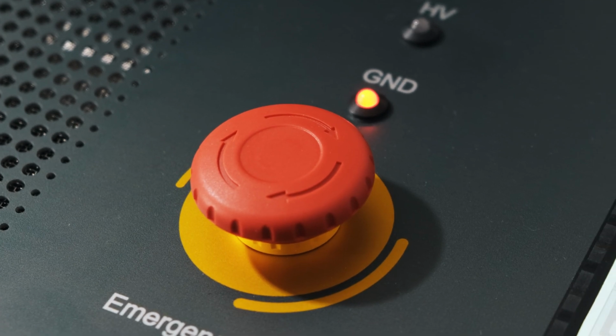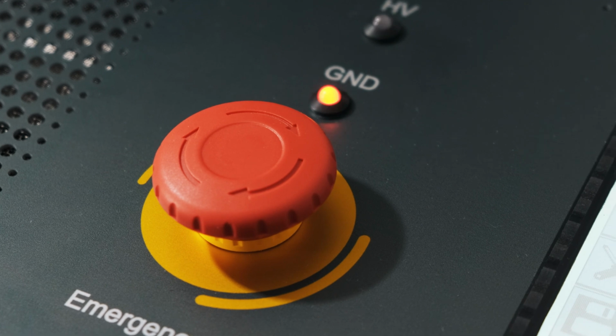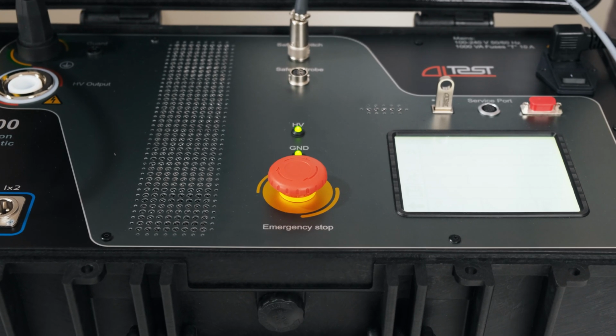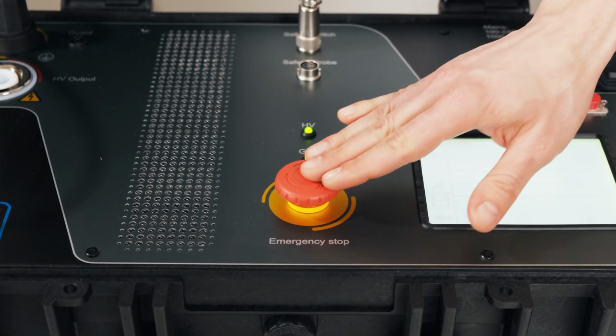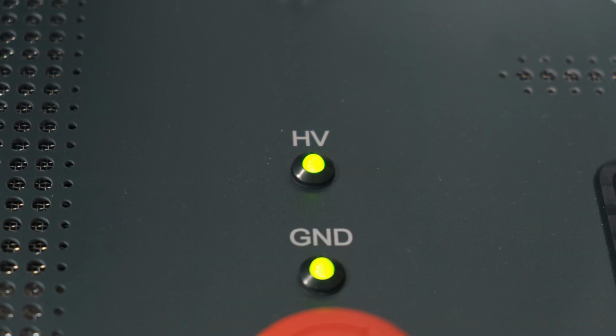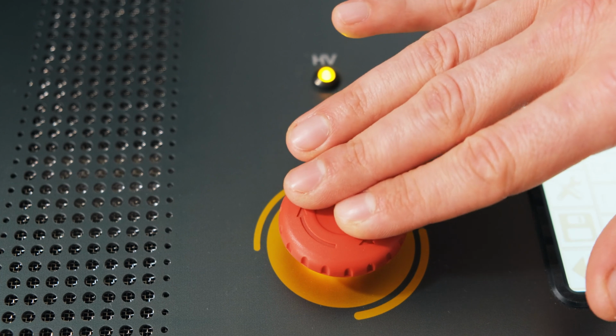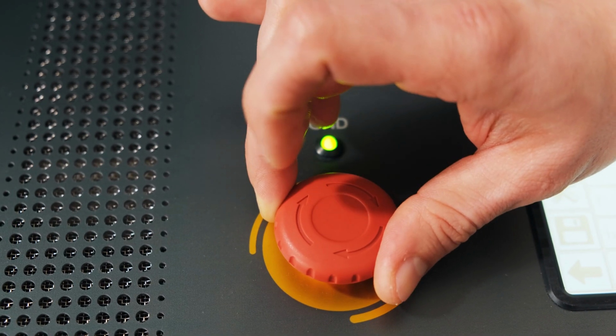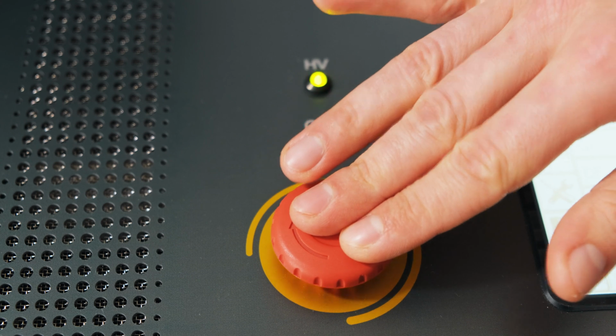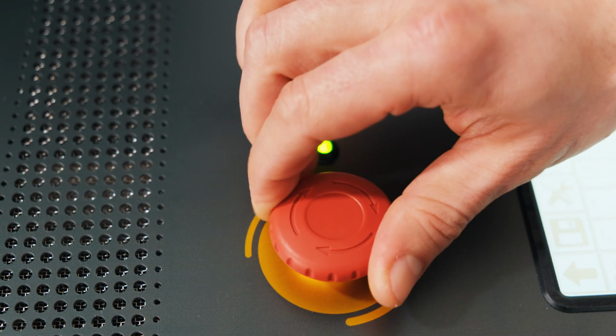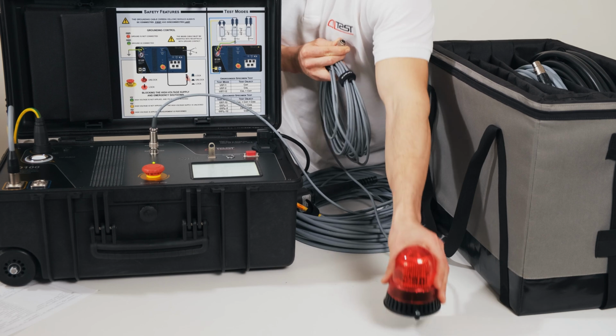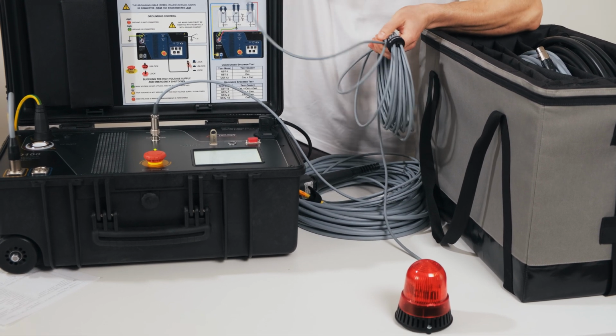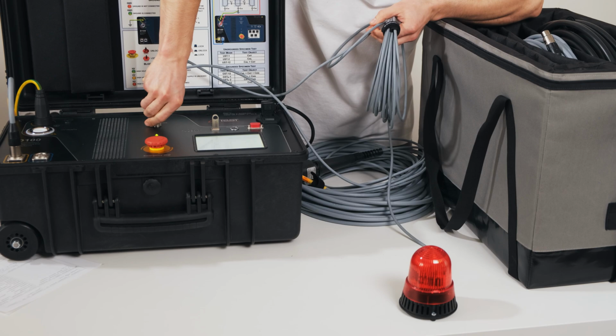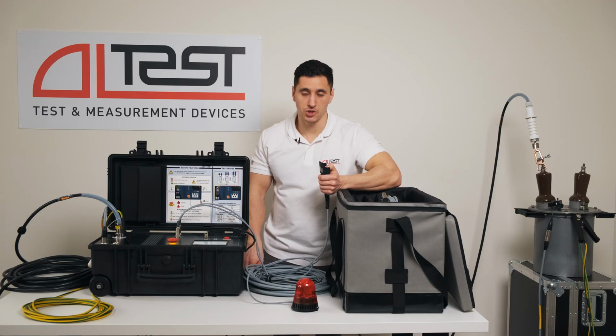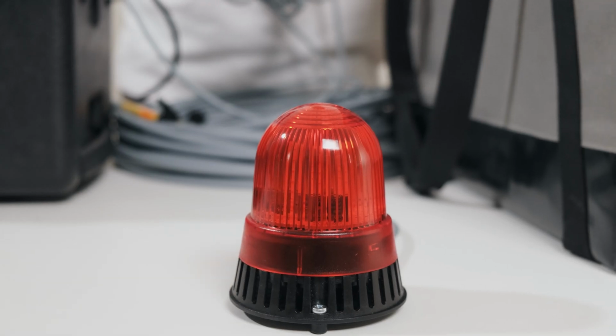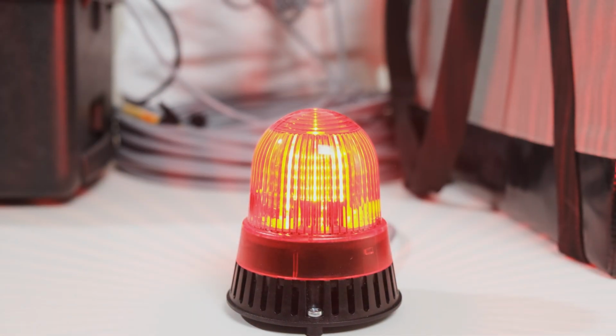The emergency stop button is located on the front panel of the device and is used for emergency removal of the operating voltage and shutdown of the testing process in dangerous and unforeseen situations. When the emergency stop button is pressed, the high-voltage supply is locked. It is necessary to rotate the button to unlock it. Also, you can order a safety strobe light that is connected to the corresponding socket. When high voltage is applied to the measuring circuit, the safety strobe light emits light and sound signals.